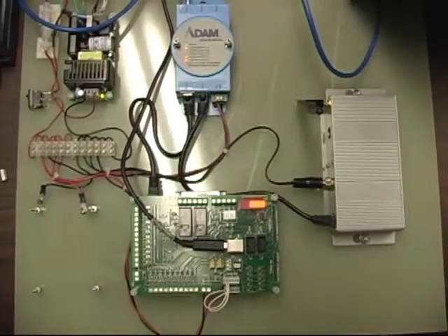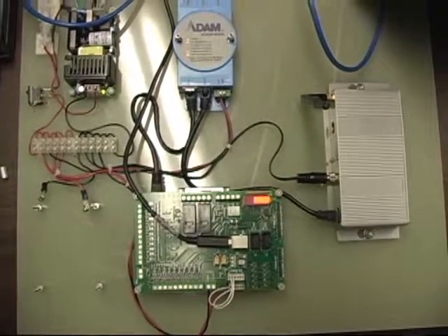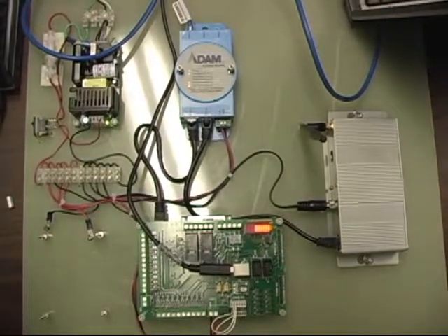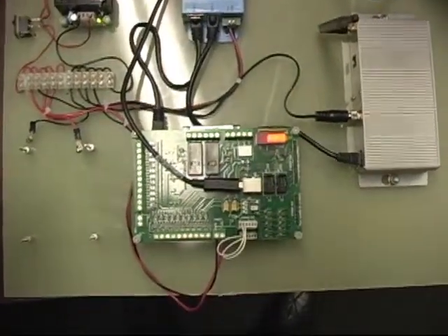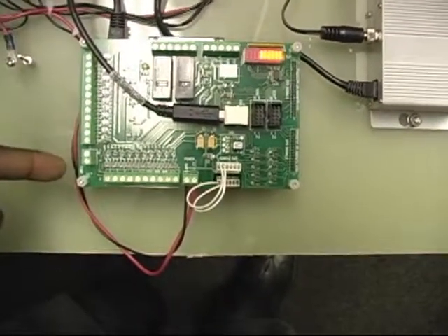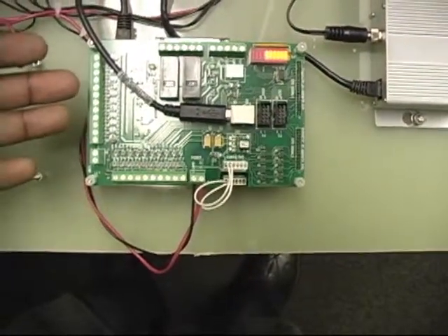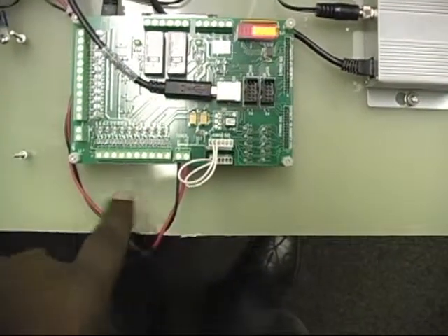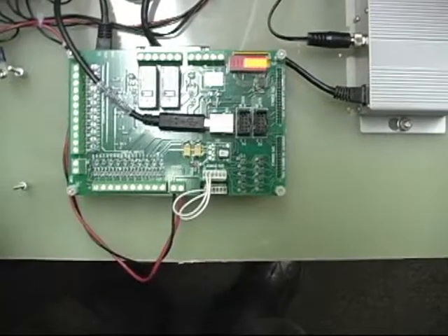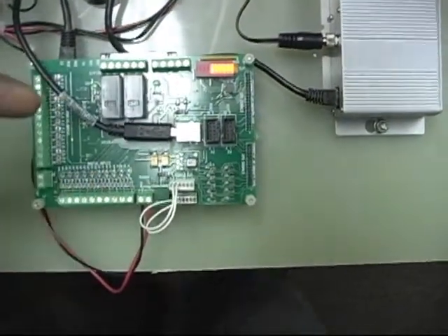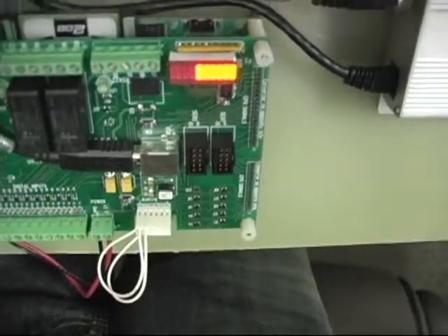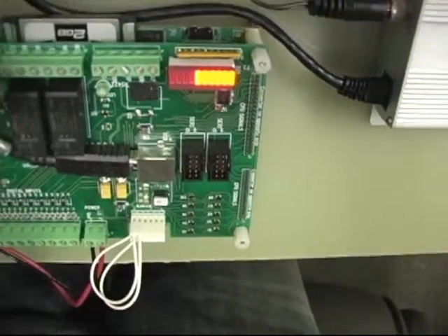Our system allows you to measure your current from your transformer to be able to determine the load share that you are using. Essentially, we have analog input channels at this node, as you can see, that takes in the current measurement. Or if you had digital signals, you can also have them entered in through here. And what happens then is that this data is taken in by the embedded PC board that is laid right under our motherboard, as you can see there.